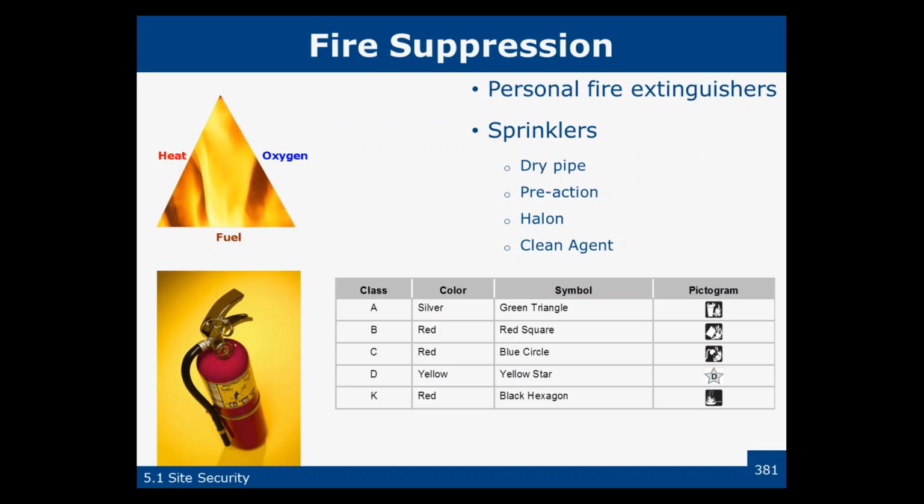The sprinkler heads could fail, and those types of things. A dry pipe is used if you have a freeze hazard or things like that. The dry pipe doesn't have water in the piping itself, but it's filled when the sprinkler system is activated. To me, one of the big disadvantages of the wet pipe is that the water's been sitting there for years in some cases. It can be pretty nasty when you do these things. A pre-action system fills with water when an alarm is triggered, and it will then spray when the heat rises.